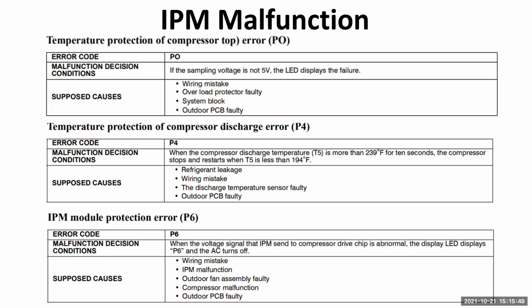You want to check your refrigerant level for these error codes. And there's only one sure way to verify you have the correct refrigerant level, and that is to recover your refrigerant, weigh it out as you're recovering it, compare it to the data plate or any extra line length you have to add for it. And obviously, if you're low, then you have a refrigerant leak someplace and need to track that down.